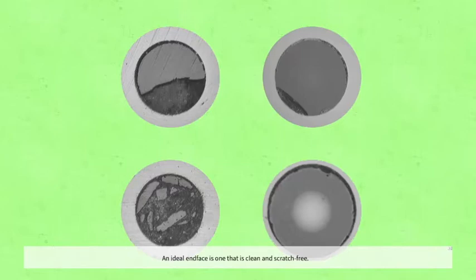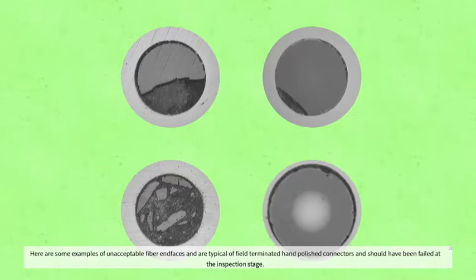An ideal end face is one that is clean and scratch-free. Here are some examples of unacceptable fiber end faces that are typical of field-terminated hand-polished connectors and should have been failed at the inspection stage.